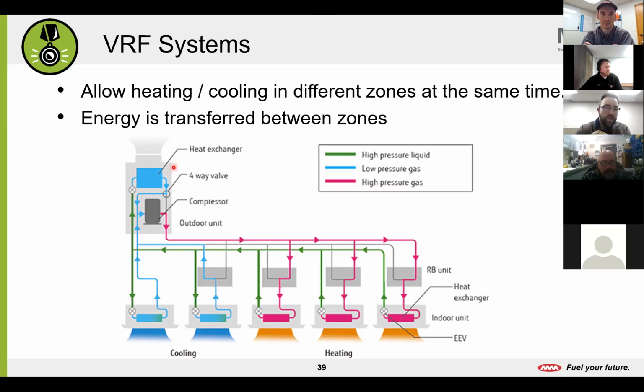If we have a branch controller in here that is already in place, and say we need to add another zone, or we're doing some kind of changes to the space, we can actually go off of that branch controller, this branch box, and run another line set or copper refrigerant pipes to an indoor unit, say a wall mount or a ducted unit, anything have you, and actually add to that system. And of course, there's some minor adjustments that'll have to be made to the capacity of the outdoor unit, but it definitely allows us to have a lot more flexibility on that front.